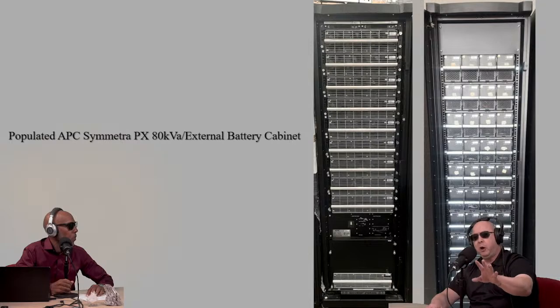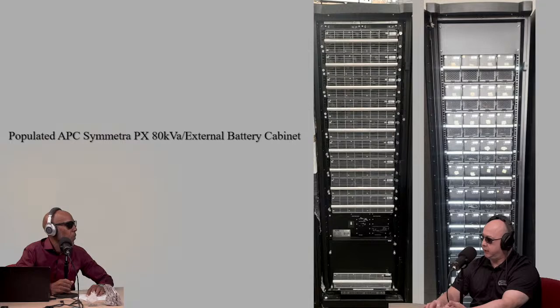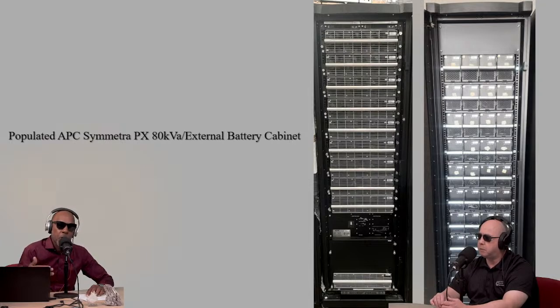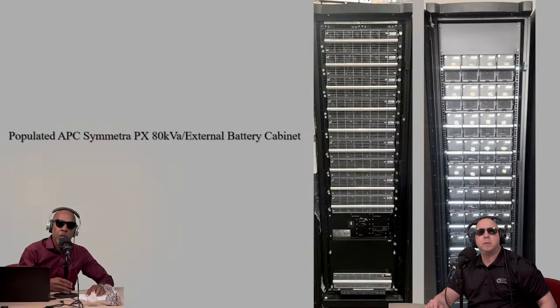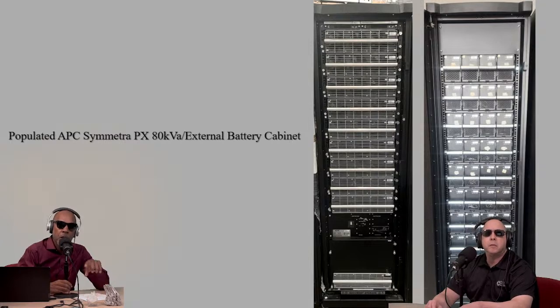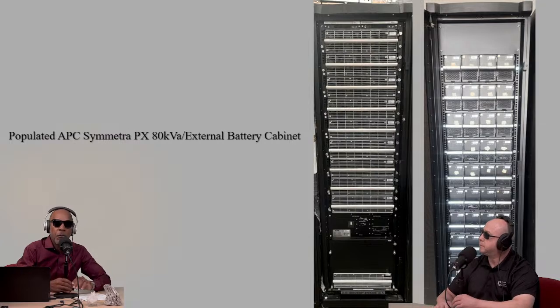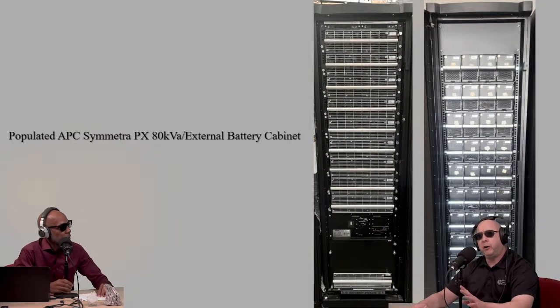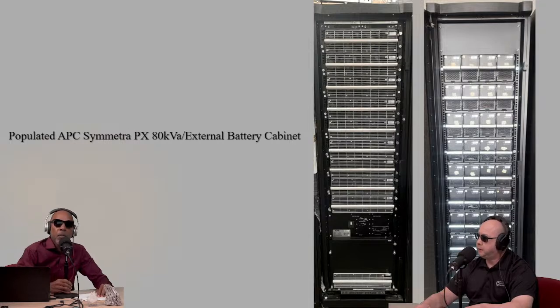By labeling it, we've already taken the guesswork out of which one fits and works in which slot. Question: is it typical to run without full use of slots? Most of the time, yes. We do send out fully populated UPSs, but the reason you have a modular UPS is because most of the time the customer doesn't need all the slots. They're getting the frame for growth, and if they add more devices later, they buy another power module to fill that slot. So most modular UPSs we send out, whether an LX or a PX, typically aren't fully populated. Surprisingly, the last 4 LXs I've done have not been fully populated. So it does happen.